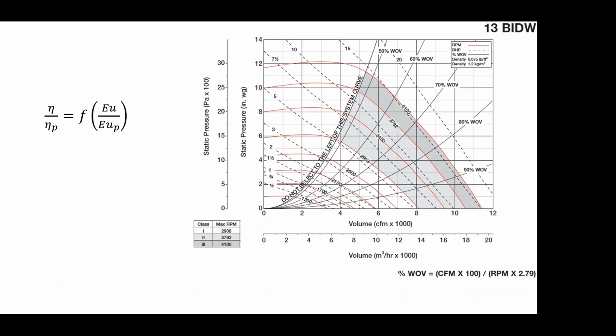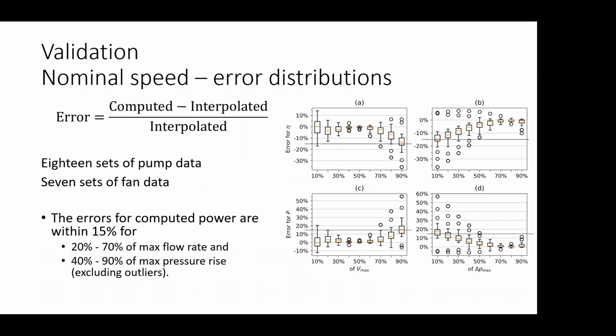I think the reason is that we weren't very precise about locating the peak efficiency on the fan's power map. As mentioned, we searched along the line of maximum speed, but the actual global peak efficiency probably occurs somewhere higher, in a region the fan isn't intended to run in. Because we underestimated peak efficiency, the efficiency computed at any operating point based on that reference was also consistently underestimated.